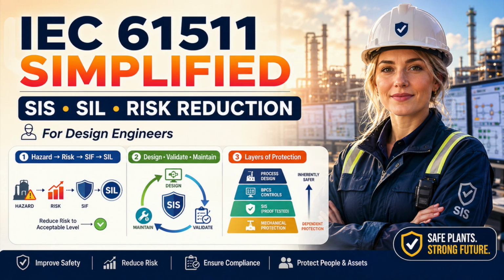Every safety-related change should ask the same questions. Has the hazard changed? Has the initiating frequency changed? Has the consequence changed? Has the process safety time changed? Has independence changed? Has the proof test effectiveness changed? Has the demand rate changed? Does the required integrity remain valid?